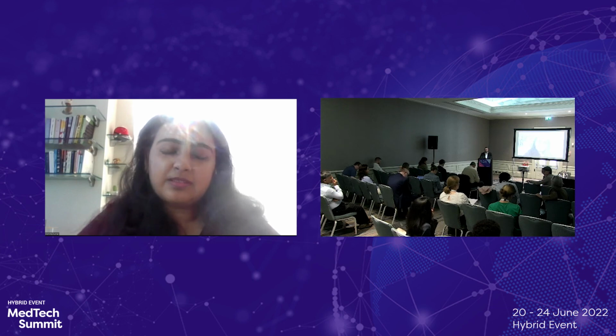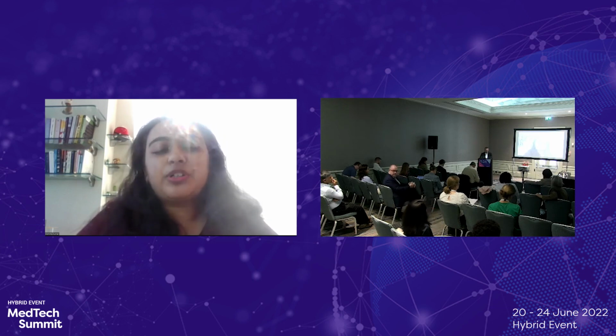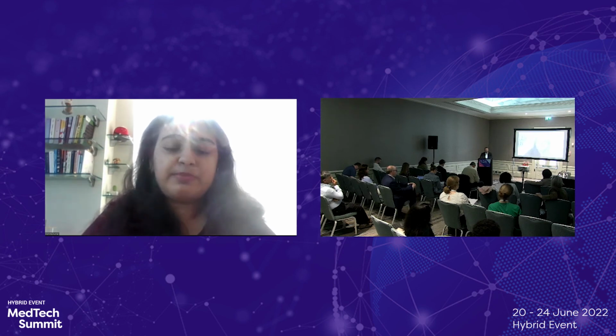Any comments there? Yeah, I think it's important to work on the CER and SSCP parallelly for this. Parallelly in the sense that we stagger it a little bit. The SSCP comes after the CER. So we work on them sort of parallelly, so the review processes happen parallelly then. Every time you get feedback on the SSCP, that's going to feed into the CER at that point.